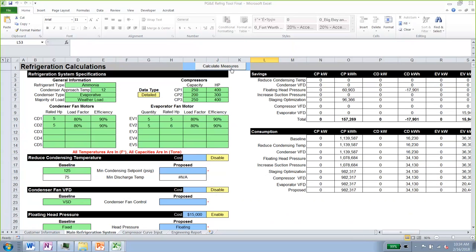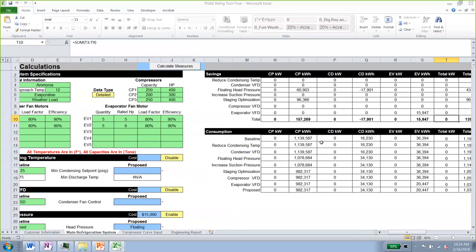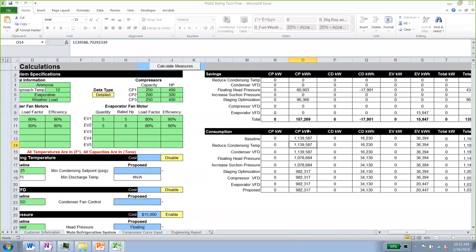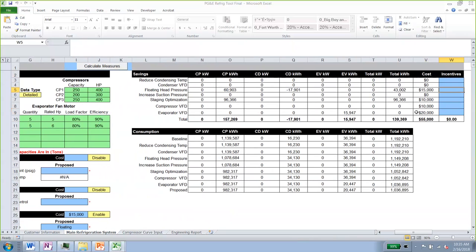The recalculation is complete. Note that calculations typically take 30 to 40 seconds; we paused the recording to avoid downtime. Now that the evaporator measure is enabled, we're getting savings. Results are broken down by equipment type — compressor, condenser, and evaporator. Floating head pressure gives positive savings on the compressor and negative on the condenser. Staging optimization gives savings on the compressor only. Evaporator VFDs show savings only on the evaporator.